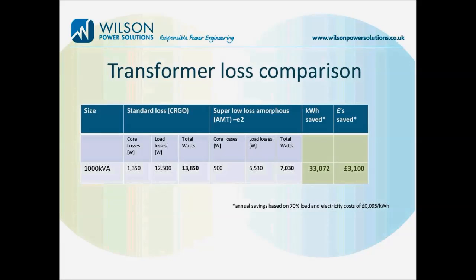Let's just have a look here at this loss comparison chart. It shows loss values for a typical 1000 kVA transformer, and it compares a conventional standard CRGO transformer with the second generation of the Wilson E2. As you can see, the combined losses for the CRGO units there are just under 14,000 watts, and those for the super low loss amorphous are just over 7,000. So roughly speaking, losses are halved, as we'd said earlier, in the Wilson E2.